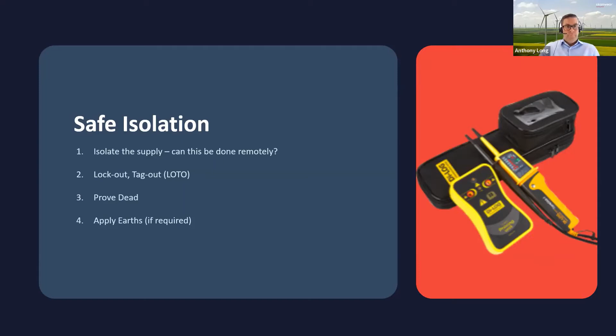So many situations we see proving dead isn't taking place. And if proving dead isn't taking place, you come to remove a panel, to do some work on a panel. Unless you've proved it's dead, that panel is still live. And so many injuries, so many fatalities we find is when people haven't proved dead, open up panels and start to work on panels that are still live. And as a result, you get either fatal or really critical consequences coming out of that. And obviously, certain systems are set up to already manually earth, but otherwise, you can apply the earth yourself. It gives you a backup in case something gets energized in the process.